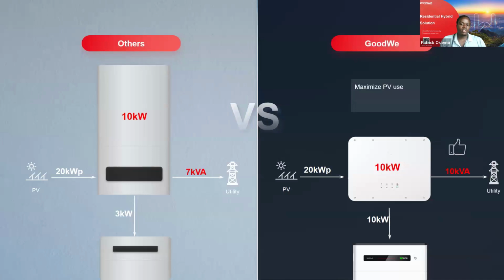Contrary to other inverters, the ES Unique is capable of doing DC to DC charging of the batteries. On the left side, you can see other inverters rated at 10 kilowatt. If they're oversized up to 20 kilowatt, at the AC output side they can only output 7 kilowatt, and if enough is generated, they output 3 kilowatt to charge the battery. So in total, it's outputting 10 kilowatt at max. Comparing that to the ES Unique, which maximizes the PV for self-consumption: if you oversize the PV to double the size of a 10 kilowatt inverter, it can output 10 kilowatt on the AC side, and on the DC side the same inverter outputs 10 kilowatt to charge the battery. So basically, you are outputting power worth 20 kilowatt, double the inverter rating. So that's the uniqueness of the GoodWe ES Unique.